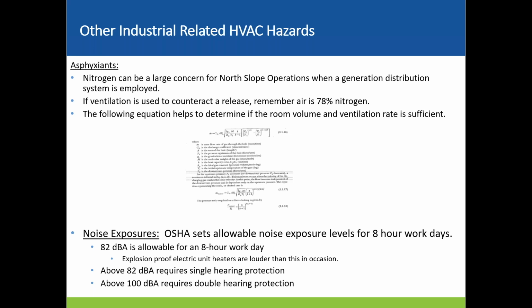Noise exposures, another big one. OSHA sets those allowable noise exposures for 8-hour workdays. The 82 decibels is allowed for your 8-hour workday. And explosion-proof electric unit heaters are louder than this a lot of the time, especially if you get into 25 or 30 kW models. Something to be considerate of. It's not awesome when the HVAC equipment is what's causing hearing protection requirements in your buildings. Really, you'll see that the two thresholds are 82 and 100 decibels, which requires double hearing protection. That's what's driving that when you're in facilities.